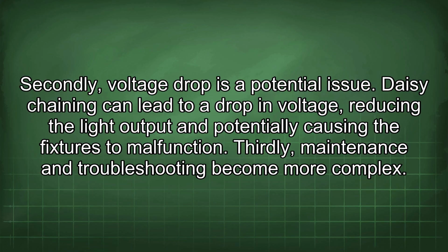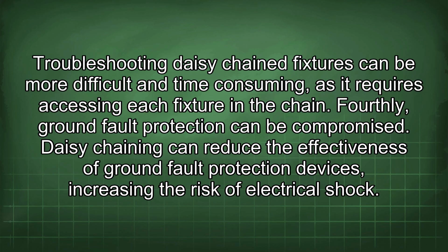Thirdly, maintenance and troubleshooting become more complex. Troubleshooting daisy chain fixtures can be more difficult and time-consuming, as it requires accessing each fixture in the chain. Fourthly, ground fault protection can be compromised. Daisy chaining can reduce the effectiveness of ground fault protection devices, increasing the risk of electrical shock.